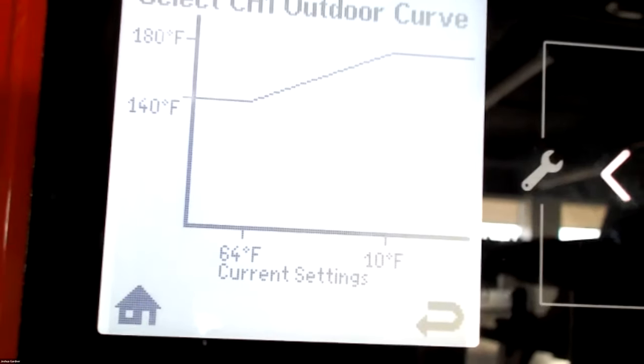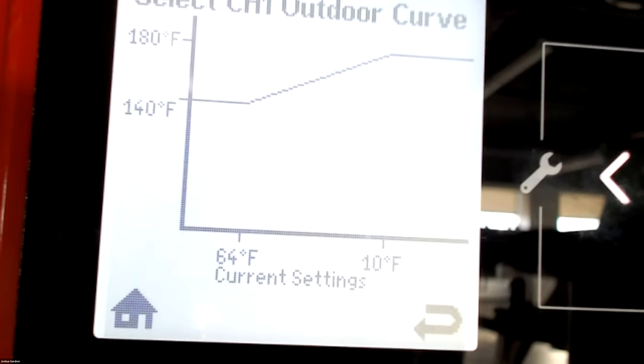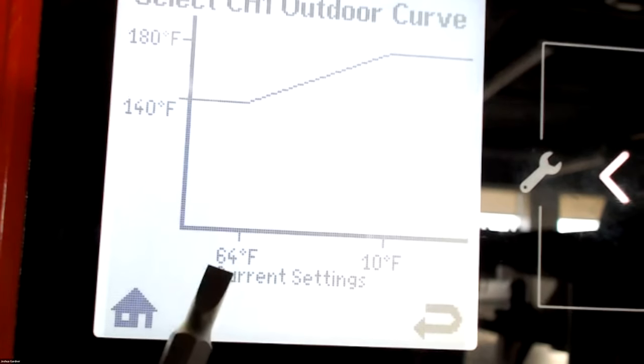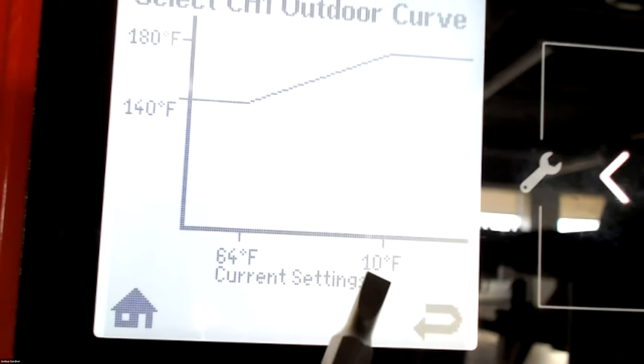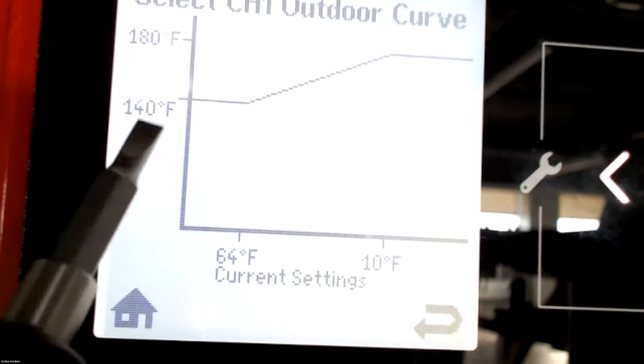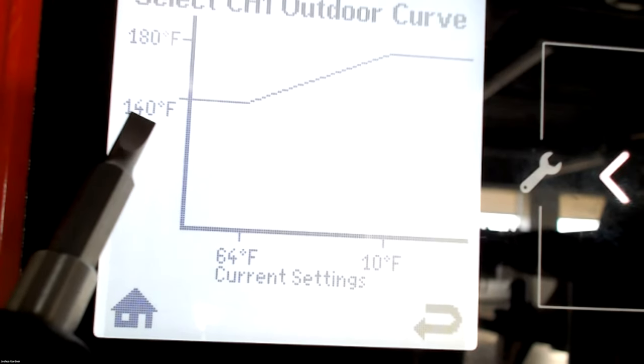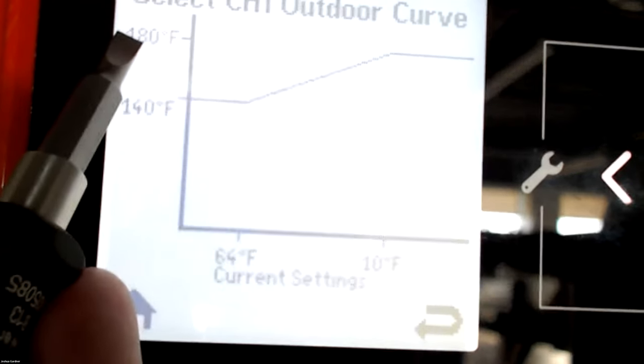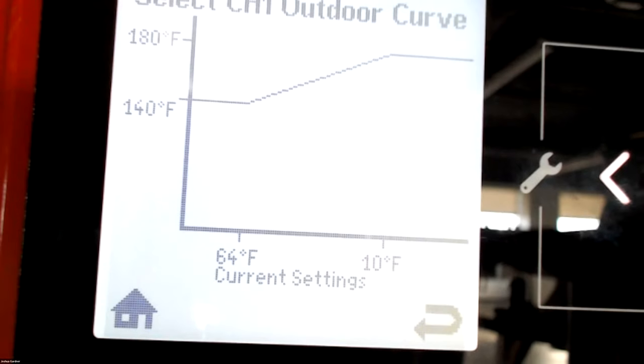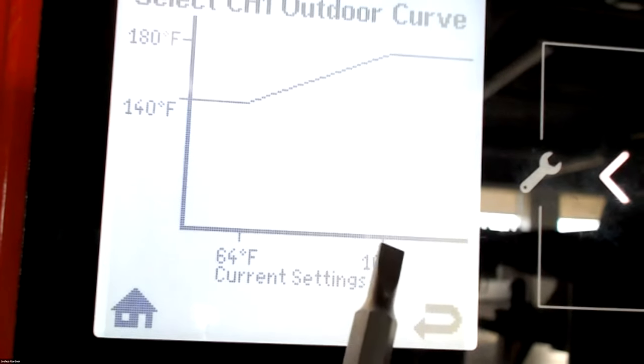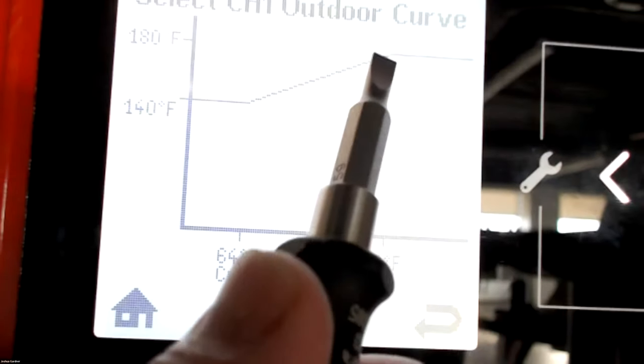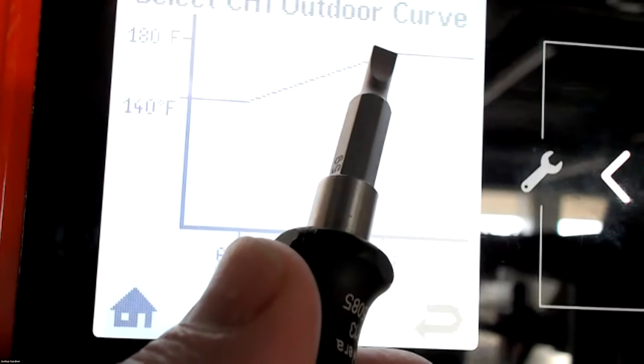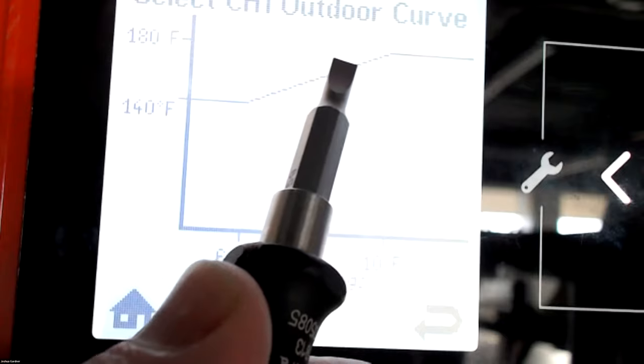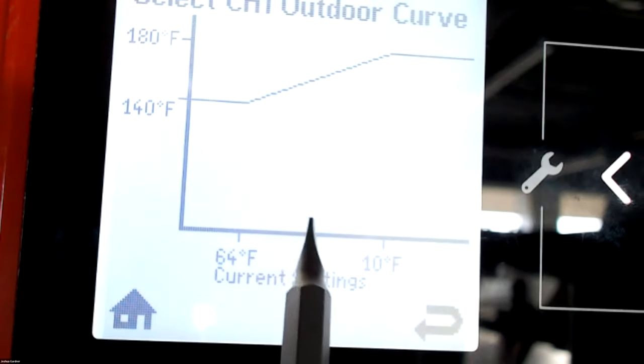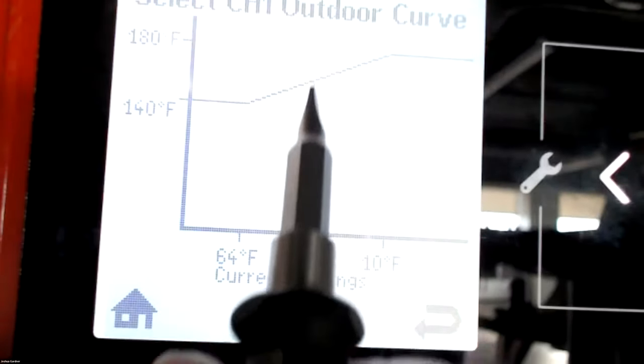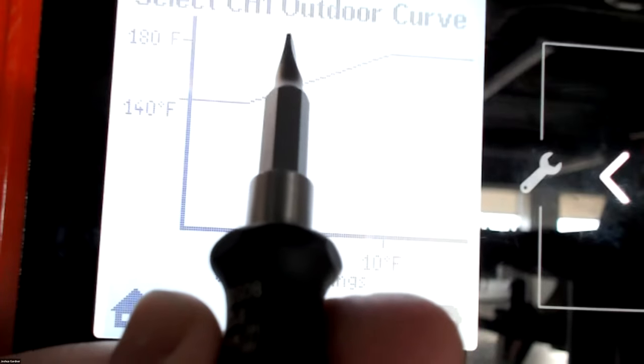So this is the current setting. What this is saying is that my warm design is 64 degrees outside. My cold design is 10 degrees. My coolest my boiler will run is 140, and the hottest my boiler will run is 180. So when it is 10 degrees outside, my boiler will get at full potential at 180. As it gets warmer outside, my boiler temp drops. So it might be, let's say 30 degrees, and I might be running at like 168, 160.